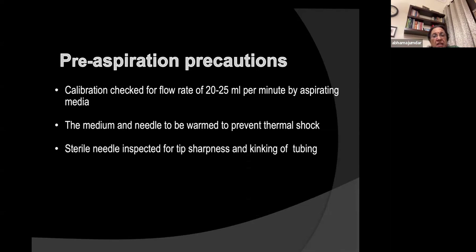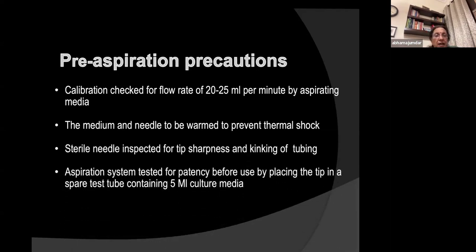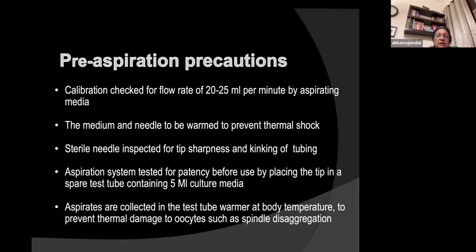Sterile needle is inspected for tip sharpness and kinking of tubing. So whenever you are opening it, you know it is sterile, you've checked the flow rate, and then when you make connections, just see that it is all watertight and there's no kinking of the tubing. Aspiration system is tested for patency before use by placing the tip in a spare test tube containing 5 ml of culture media. In fact, you can do it with even 20-25 ml of culture media. But if you only want to test patency, and this is the needle which you've been using for long and you know the flow rate, then you just use 5 ml of culture media.